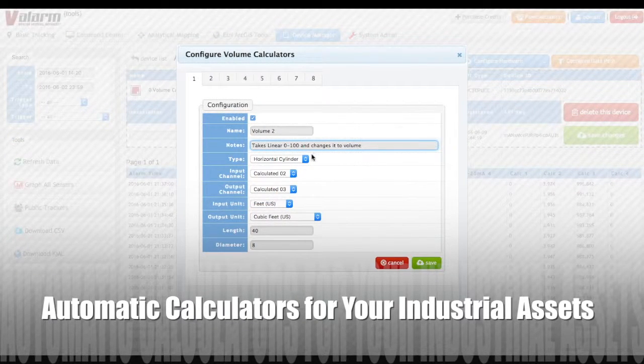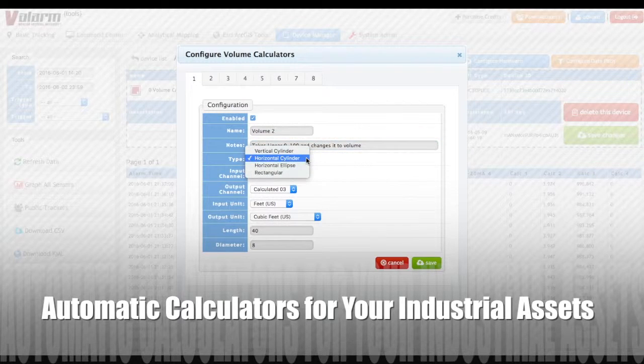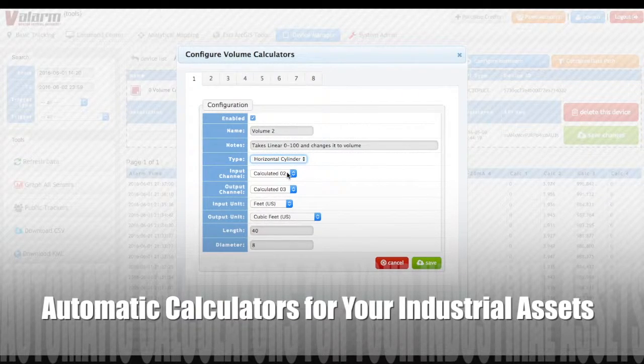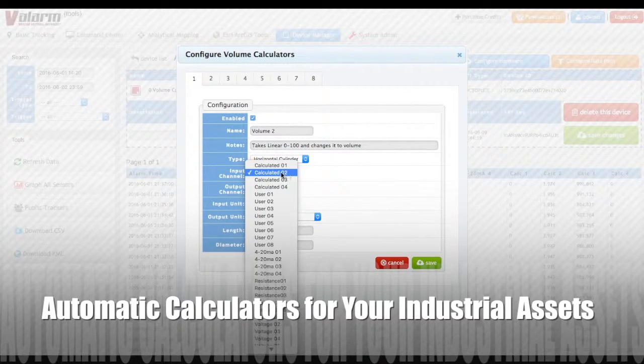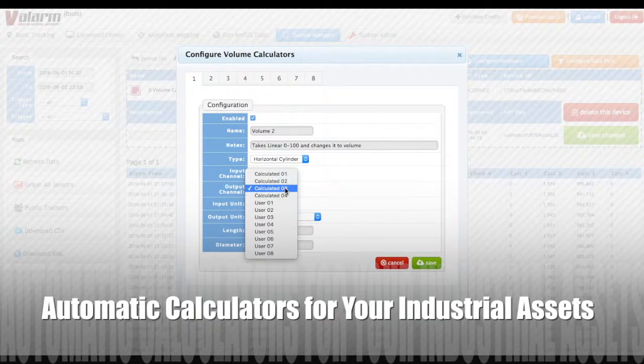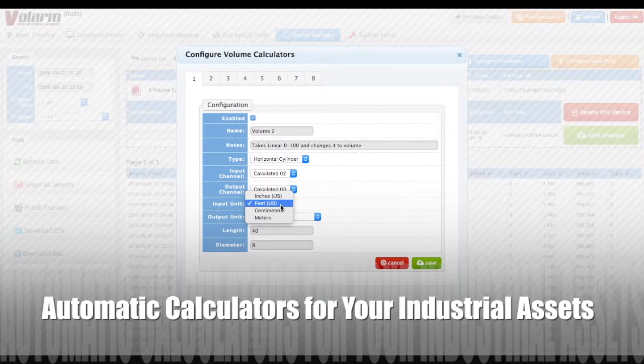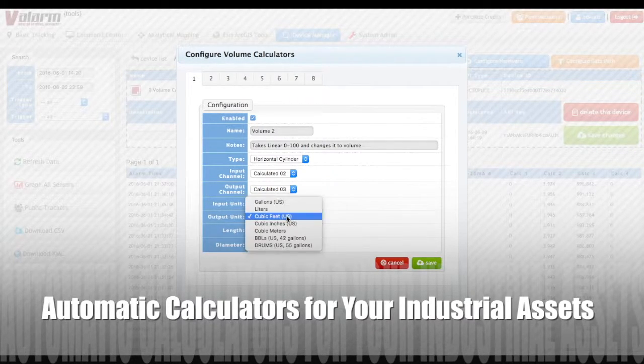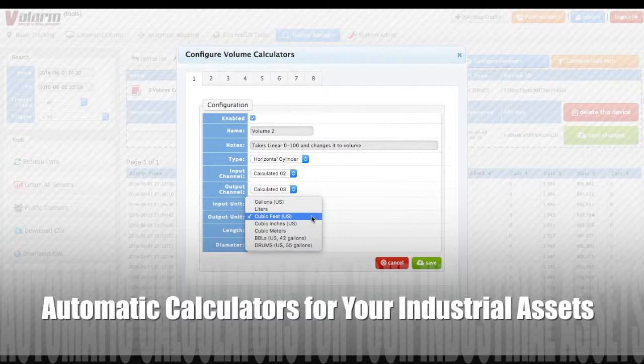When you're monitoring industrial containers like tanks, you'll likely want to know how much volume of product you've got at any time. Raw sensors can give you the height of how much fluid, liquid, or water is in your container, and the Valarm Tools Cloud feature for automatic volume calculations gives you your real-time, real-world volume values in the units you actually care about, like gallons or liters.